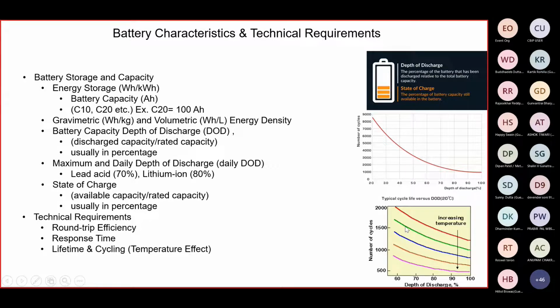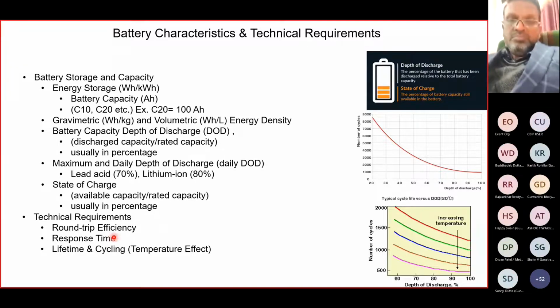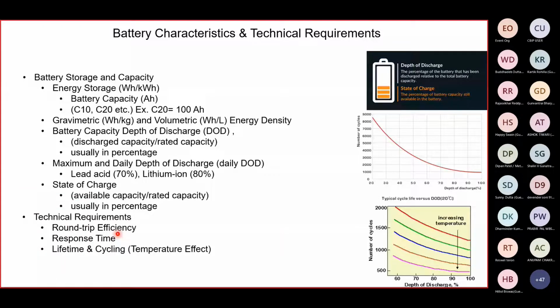You can see that if we increase the depth of discharge, we decrease the number of cycles that the battery can give. If we only discharge up to 10%, you can see that we can get the maximum number of cycles, thereby increasing the life of the batteries. The other important parameters that are looked into while designing or comparing different technologies are the round trip efficiency, response time, because the various applications would depend on how much time it is required, and whether it is an energy application or a power application, and the lifetime and cycle life that a particular chemistry can give.